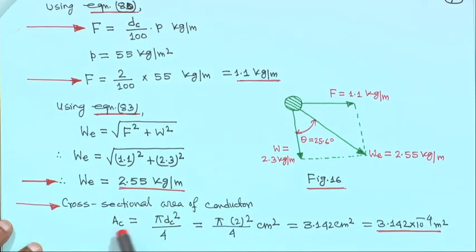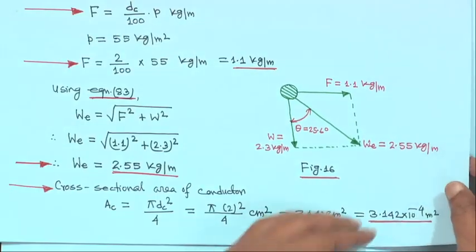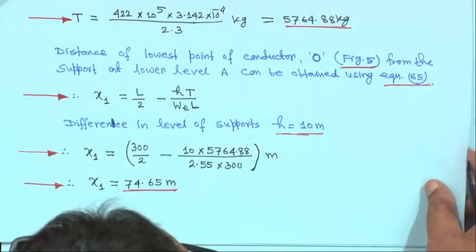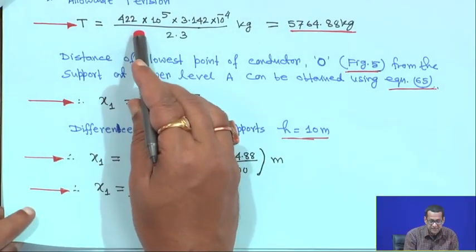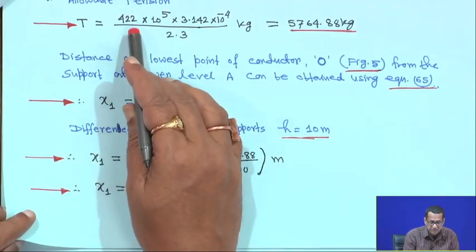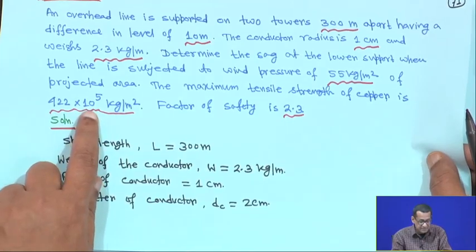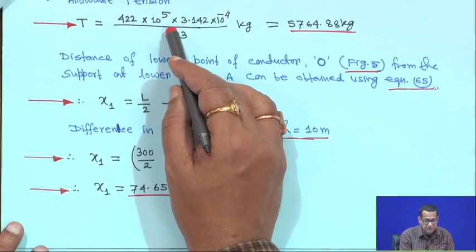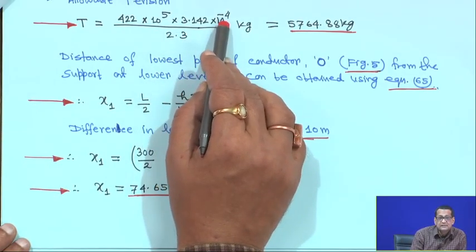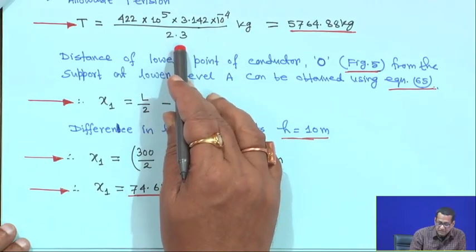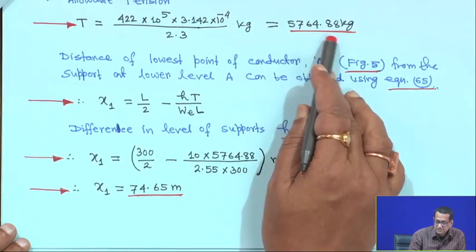Cross section area of the conductor AC is pi·DC squared by 4, that is pi into 2 squared upon 4, giving 3.142 centimeter squared, converted to 3.142 into 10 to the power minus 4 meter squared. Allowable tension: factor of safety is 2.3, and maximum tensile strength is 422 into 10 to the power 5 kg per meter square. So T equals 422 into 10 to the power 5 into 3.142 into 10 to the power minus 4 divided by 2.3, which is 5764.88 kg.